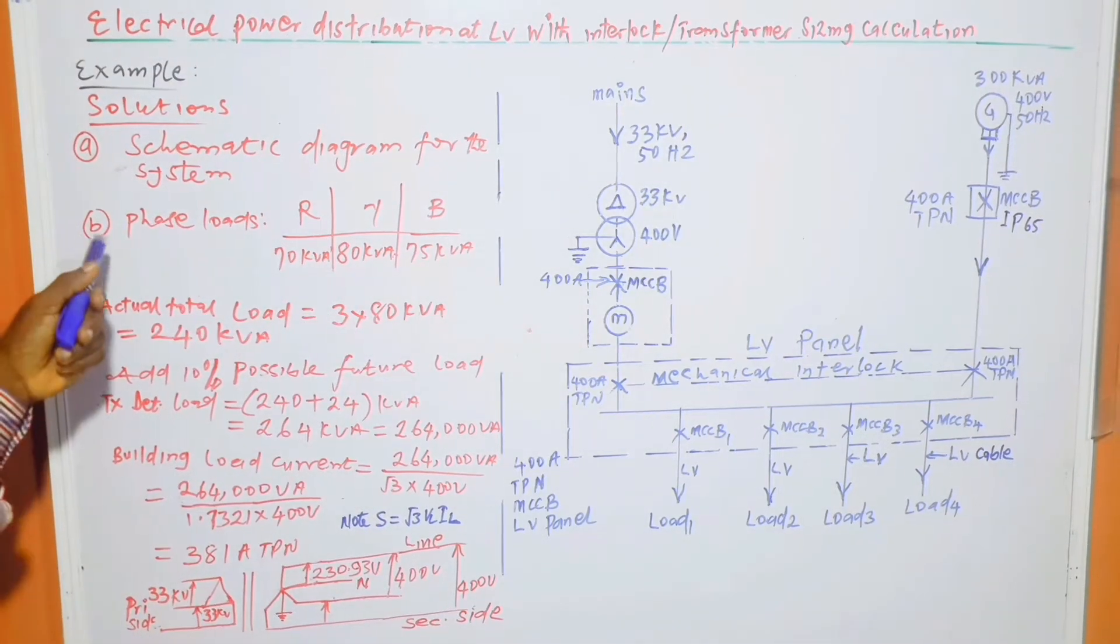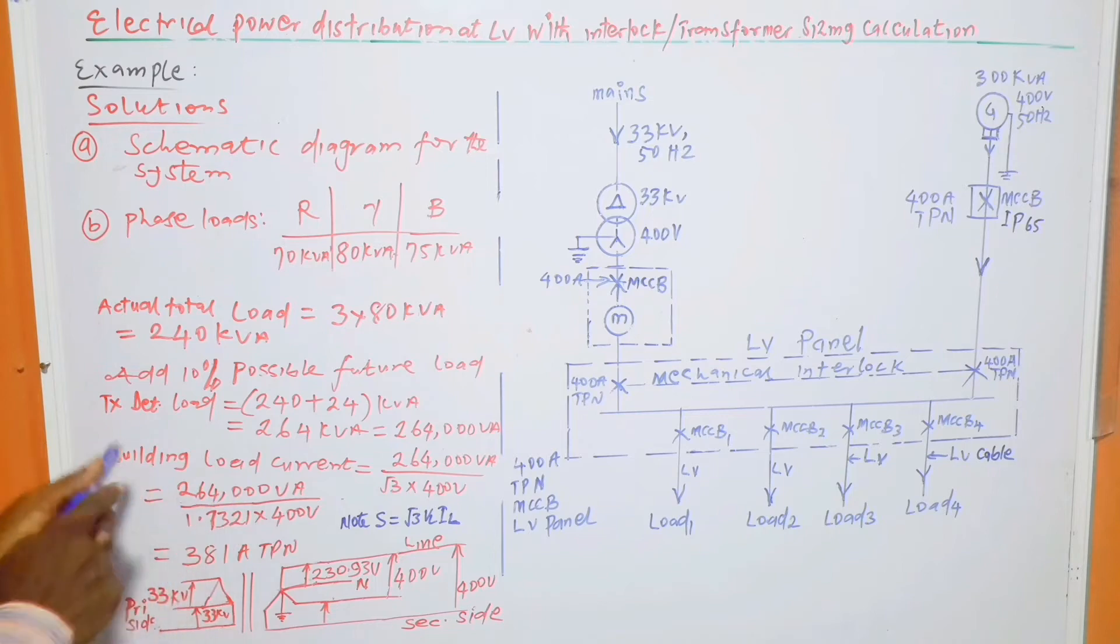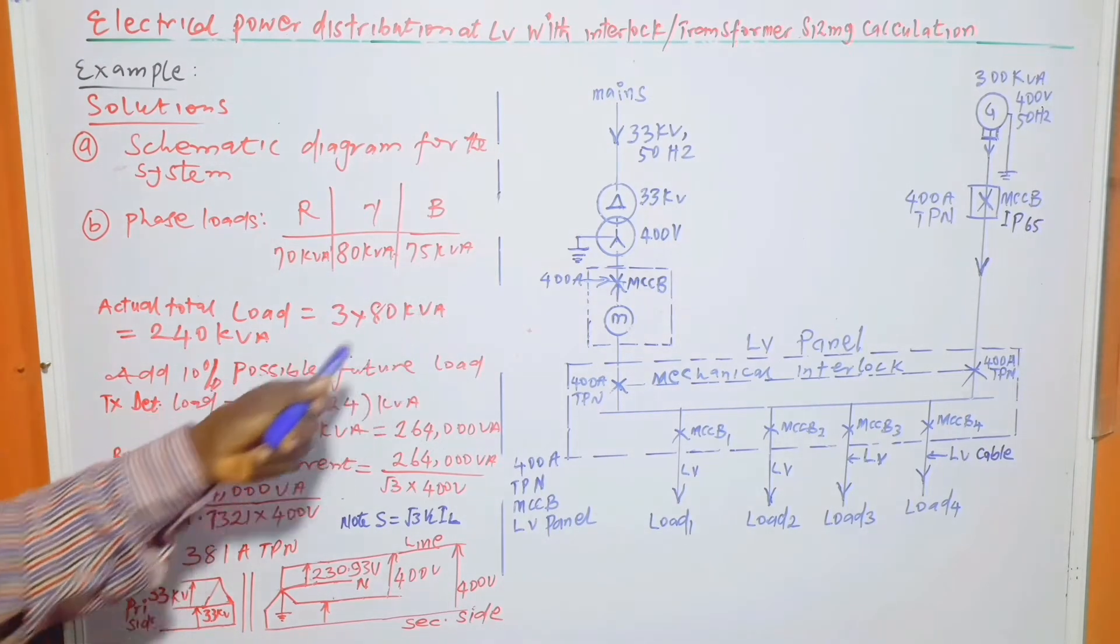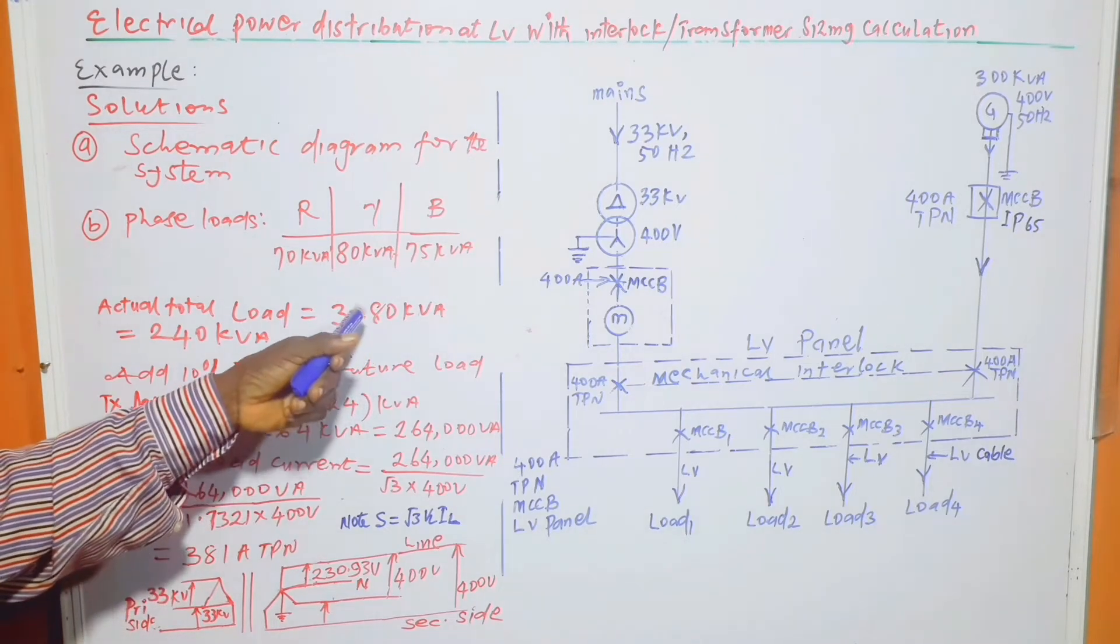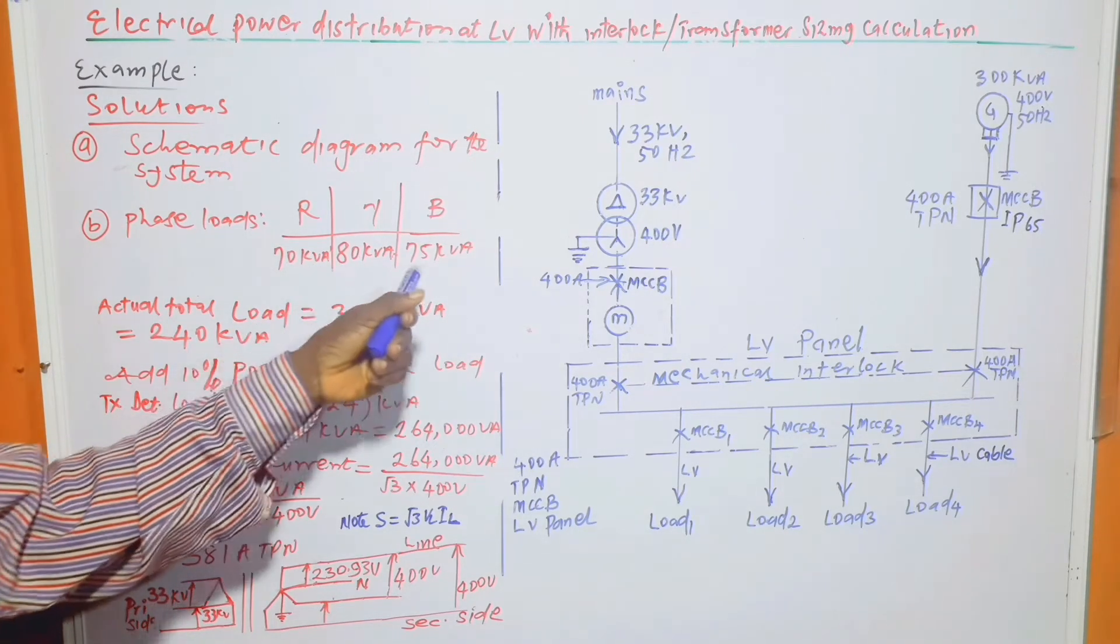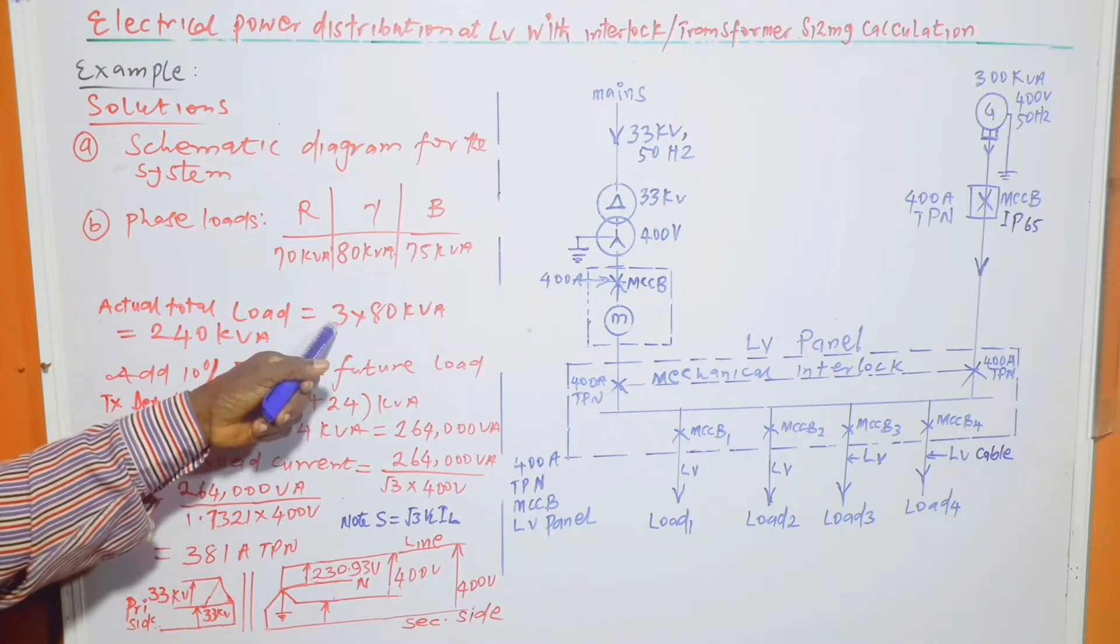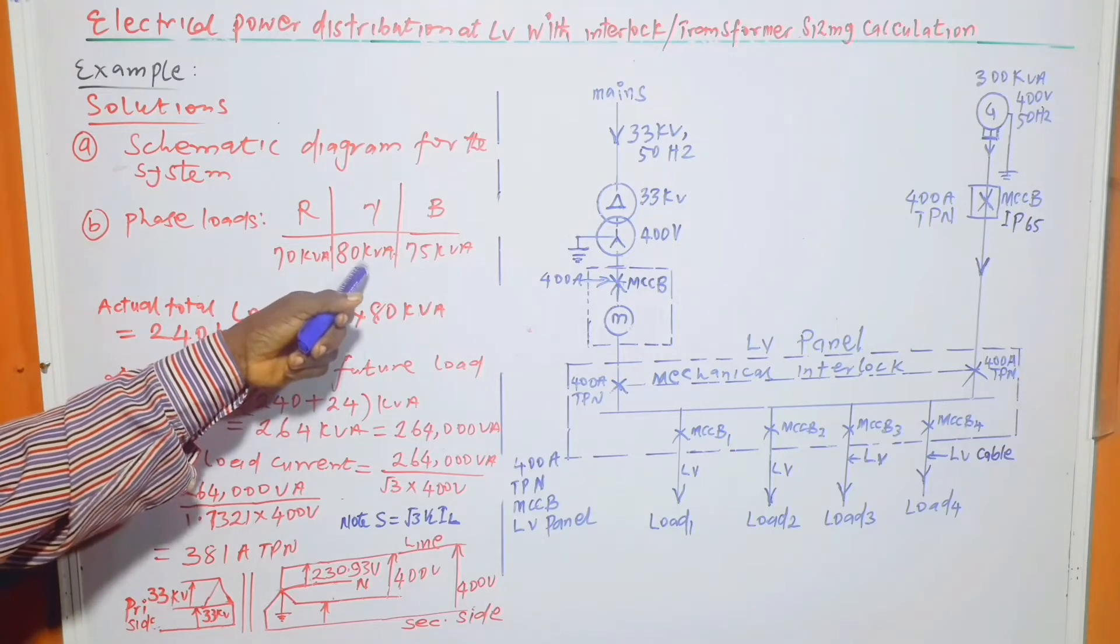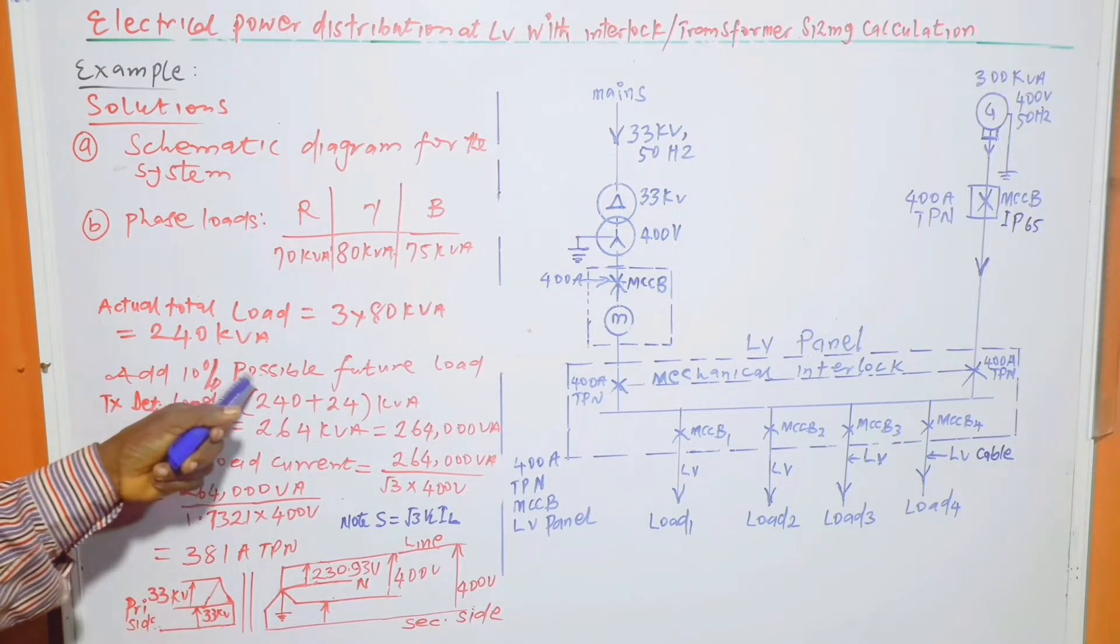Now, part B: phase loads are red phase 70 kVA, yellow phase 80 kVA, blue phase 75 kVA. Actual load is equal to 3 times 80 kVA, which is equal to 240 kVA. This 80 kVA is the highest phase load, as I explained in one of my previous videos having to do with transformer load calculation. So in this situation, you multiply 3 by the highest phase load, which is 80 kVA. You shouldn't take the algebraic sum of the phase loads.